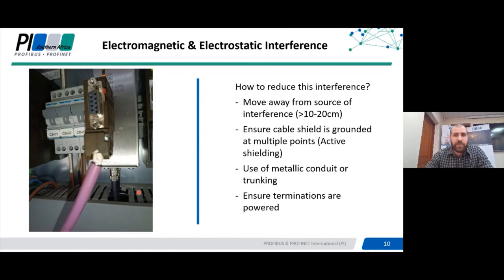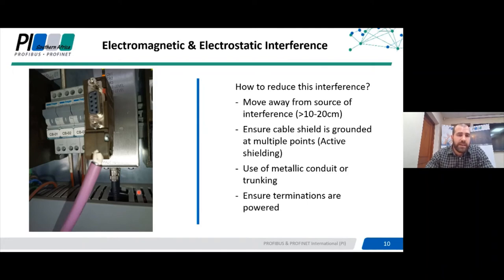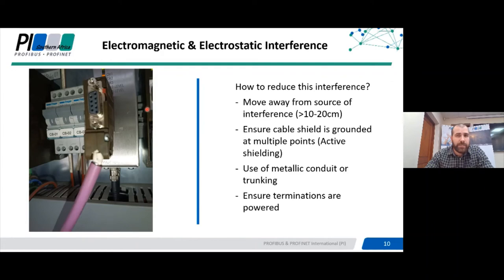It also prevents the cable from employing a defense mechanism called active shielding, which creates a counteractive force to interference if you have multiple connections of your shield to a grounding point. Where the shield connects into a cable, it connects to the chassis of the plug, which then connects to the device, which then probably drains through the DIN rail on the back plane of the panel.